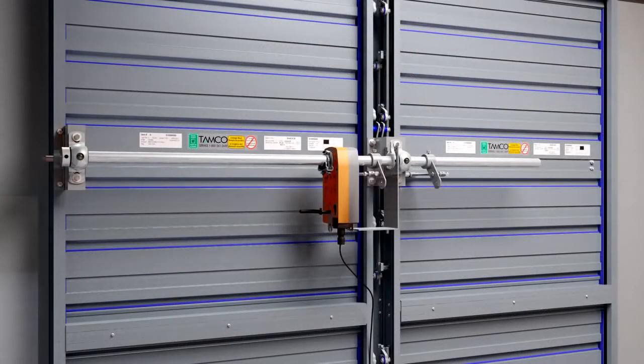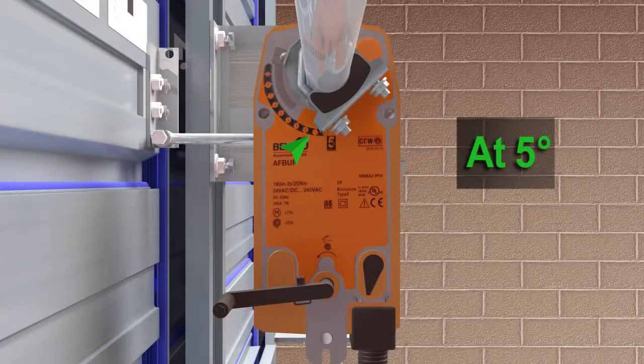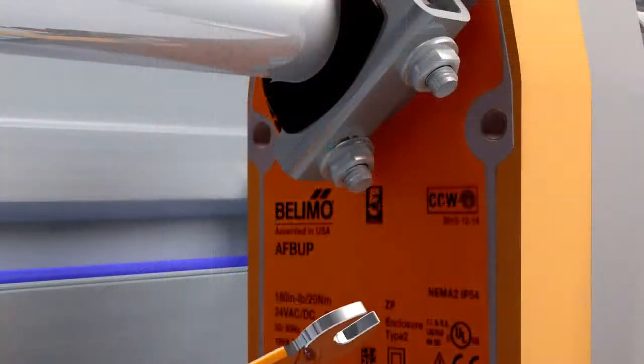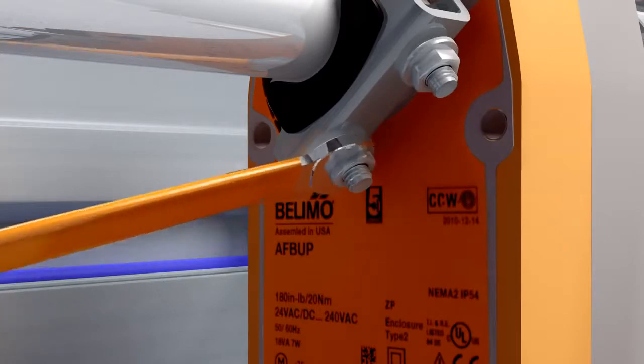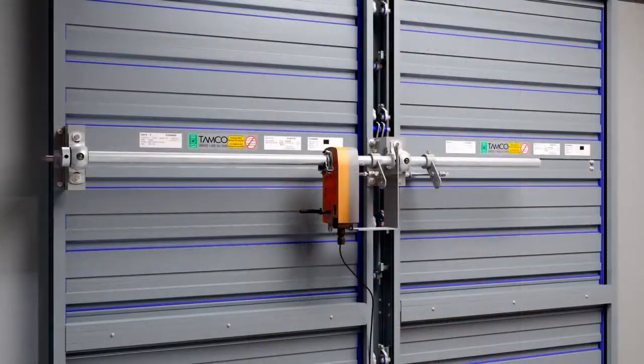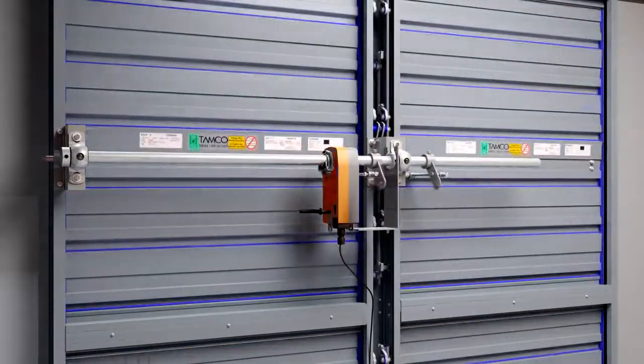Verify that the damper is still in the fail-safe position and that the actuator's universal clamp pointer tab is at 5 degrees above the full fail-safe position. Firmly tighten the V-bolt nuts using a 10 mm wrench or socket. Apply power and cycle the actuator to test that the damper opens and closes properly.